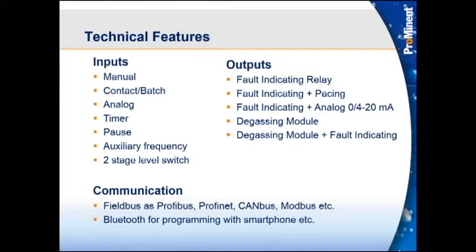You can change the dosing profile, how the suction and discharge strokes are manipulated. You can change the frequency of the pump. You can change the stroke length. You can put it in and out of automatic mode. You can also see errors on the pump on there.